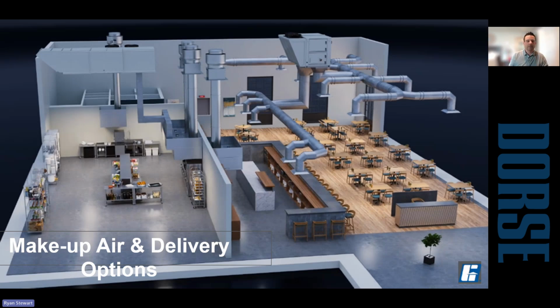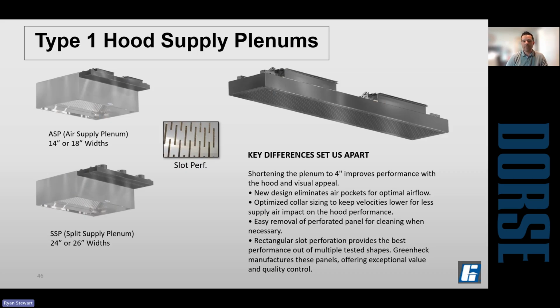Makeup air and delivery options. This is a real important part of having a hood system that works well: how you're introducing the makeup air. So most commonly, you're going to see a compensating hood that has some type of a perforated plenum that runs along the length of the hood, and then potentially even wrapping around the left and right open sides. If you have a real high exhaust airflow, you may need to wrap those around the sides to have correct velocity of makeup air. This Greenheck one, they use a slotted perf, and what they found from testing other GRD stuff that they built is that this was most effective at reducing the velocity of the air and dispersing it evenly across the length of that plenum.